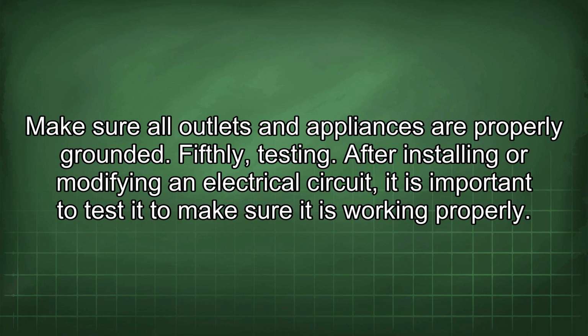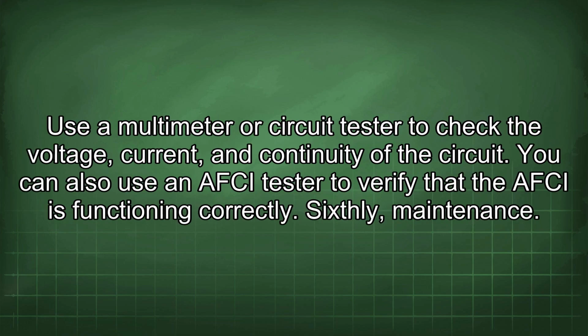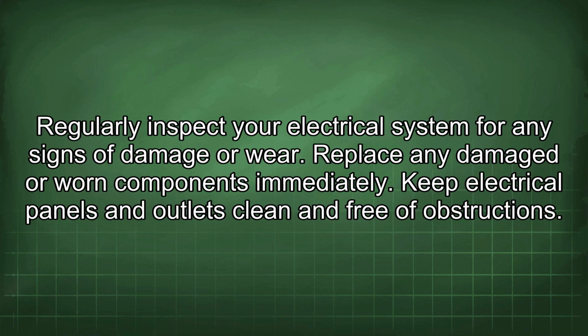Fifthly, testing. After installing or modifying an electrical circuit, it is important to test it to make sure it is working properly. Use a multimeter or circuit tester to check the voltage, current, and continuity of the circuit. You can also use an AFCI tester to verify that the AFCI is functioning correctly. Sixthly, maintenance. Regularly inspect your electrical system for any signs of damage or wear. Replace any damaged or worn components immediately. Keep electrical panels and outlets clean and free of obstructions.